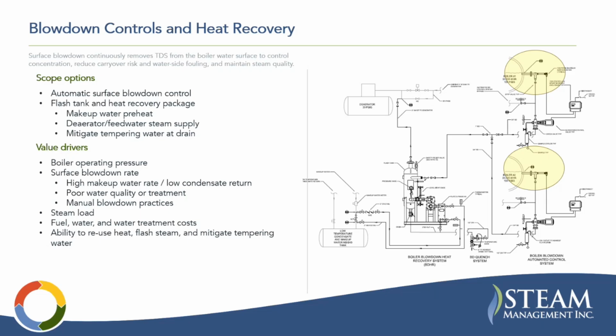More manual processes tend to have to do a conservative amount of flow in order to maintain the appropriate TDS levels in the boiler. So you're having excess blowdown, which is just wasted heat, right? Like you're heating feed water all the way up to saturation temperature, and then you're just blowing it down the drain. So it's just a total waste, but is necessary. So minimizing that is an efficiency scope in itself, but also that's a waste heat stream.